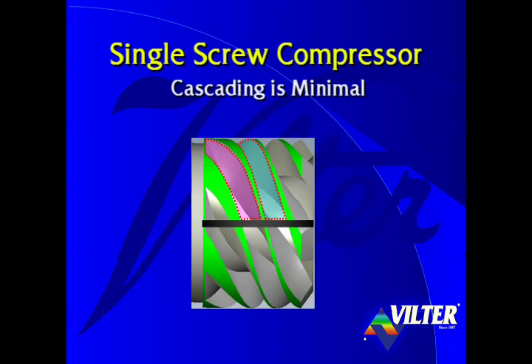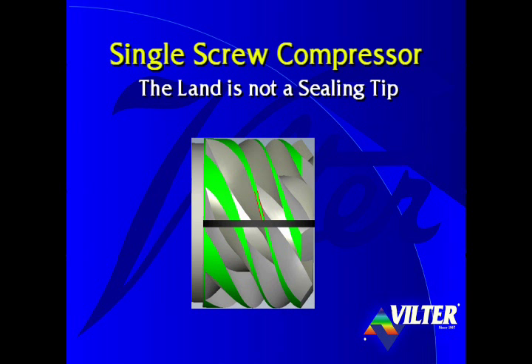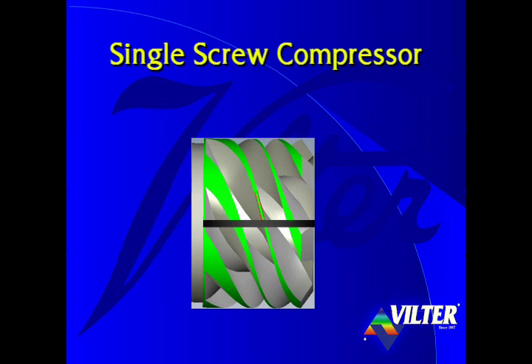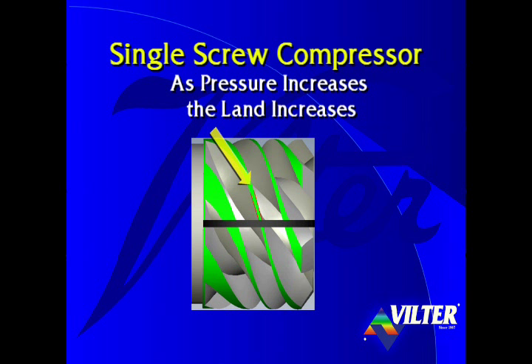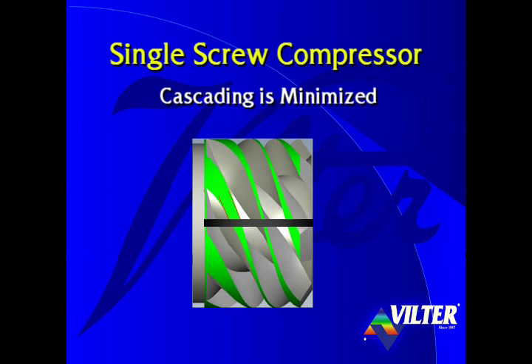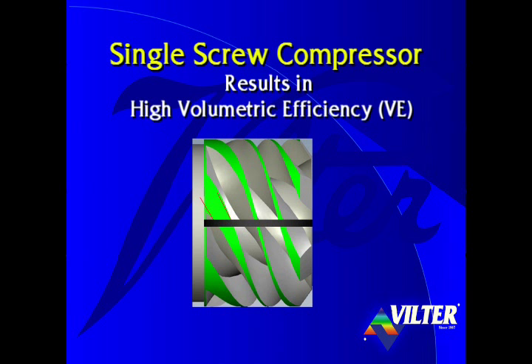With the single screw, cascading is minimal. Cascading is when gas slips across the land from a high pressure flute to the adjacent lower pressure flute. The land, which separates the flutes, is shown here in green. The land of the single screw is not a sealing tip, but rather a flat, wide surface. Notice how, as the rotor rotates and pressure increases, the land increases in width and cascading is minimized. Minimal cascading results in high volumetric efficiency.